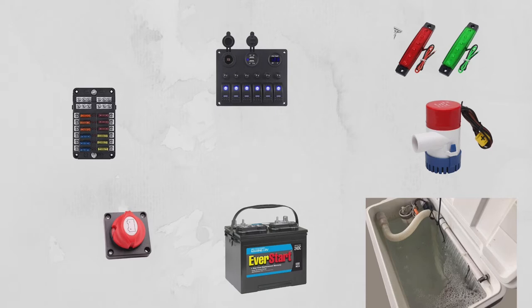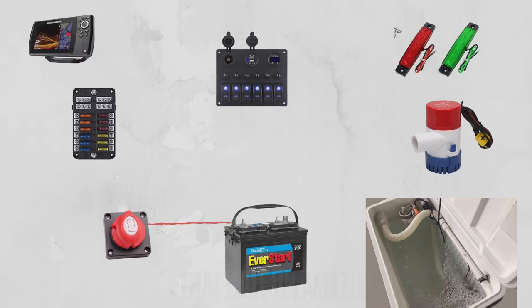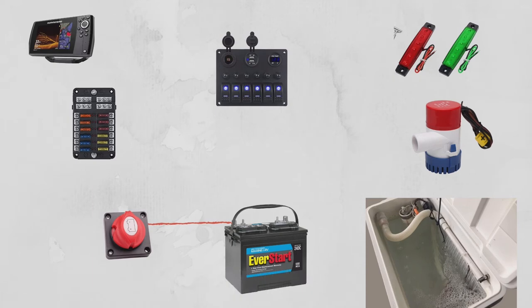A few notes before we start: positive wires are red in this diagram, and negative wires are black. Think of the current flowing through these wires like water flowing through a pipe. Too much current can heat up the wire to the point of starting a fire, so make sure you have a fire extinguisher on board. I'm going to take my six-gauge tinned marine battery wire and run it from the battery to the kill switch, and from the kill switch to the fuse box.